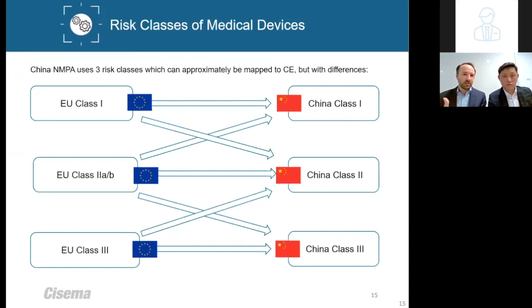Risk class, of course, determines your regulatory pathway. Class 1 medical devices go through a filing procedure. This document-based filing procedure will lead you to a certificate which is valid indefinitely, and therefore there's no renewal necessary. On the other hand, for Class 2 and 3 medical devices, the certificate that you will receive upon successful registration is valid for 5 years. This means that a renewal application is needed, and the deadline for applying for renewal is officially 6 months prior to expiration. However, we remind our clients as early as 2 years beforehand, because if the test specifications or some important standards have changed, it's possible that as part of the renewal, you have to perform some local testing, and testing takes a long time. So make sure you keep an eye on the renewal expiry of your certificate.